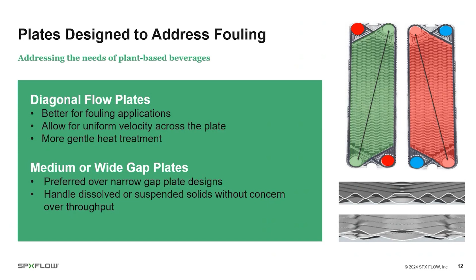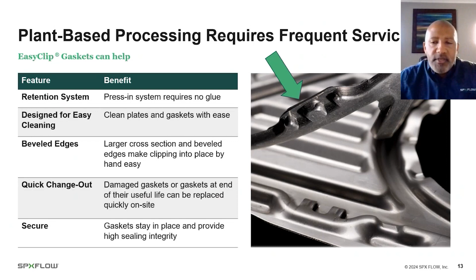Even with a well-designed plate heat exchanger, plant-based beverages with their suspended or dissolved solids will require more frequent cleaning than fluids without solids. The APV Easy Clip gaskets can help make servicing the plate pack easier. The press-in retention system requires no glue, so field service is simpler. Combined with the beveled edges, pressing the gaskets into place by hand is easy and can happen quickly on site, with gaskets staying in place and providing high sealing integrity.